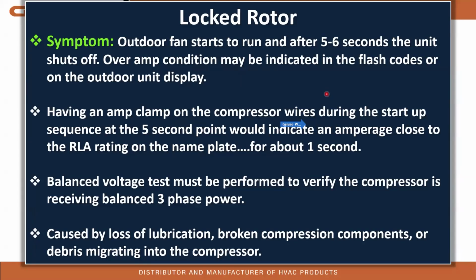To see this locked rotor condition, you would wait for another cycle of the unit, have your amp clamp on the compressor wires during the startup sequence. The fan starts, and 5 seconds after the fan starts, and this is true for every Mitsubishi M&P unit, the compressor will try to run at the 5-second mark. If it is locked rotor, you will see an amperage that is close to the run load rating on the nameplate. If that's 8 amps, 12 amps, or whatever, you will see something very high like that for about 1 second. It won't last long. The unit's going to detect that it's overamping and stop outputting voltage to the compressor.